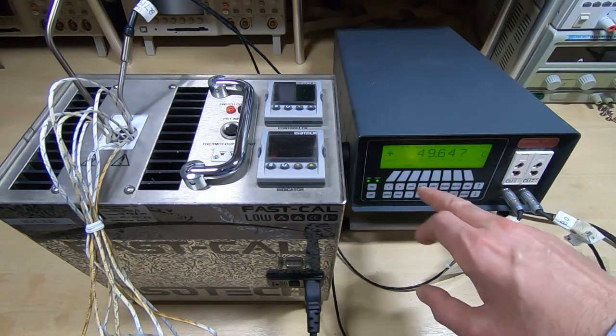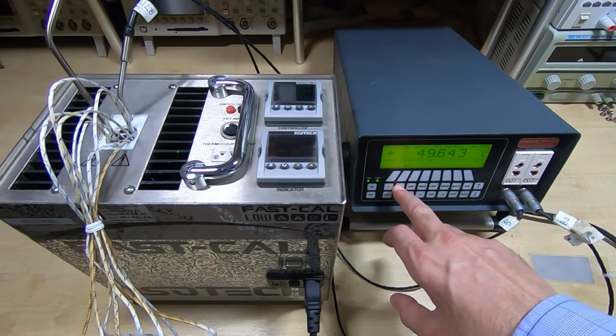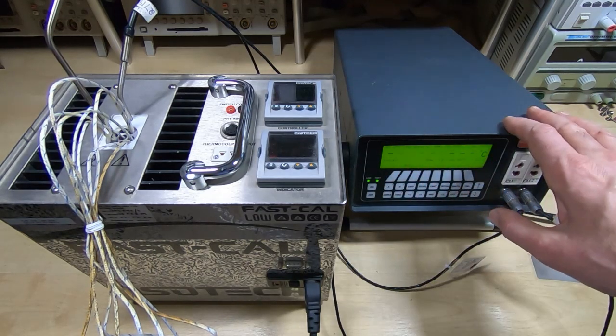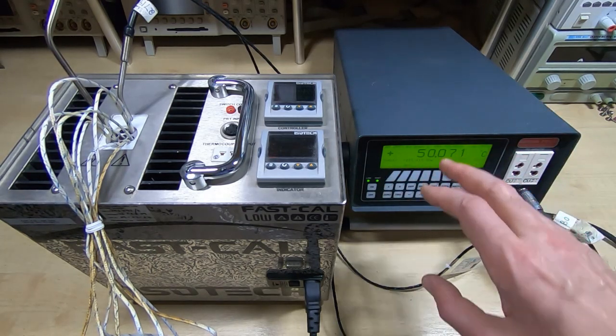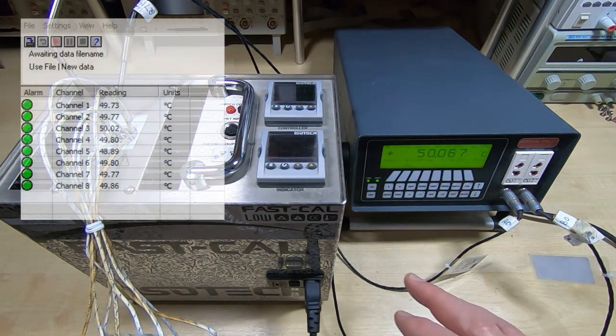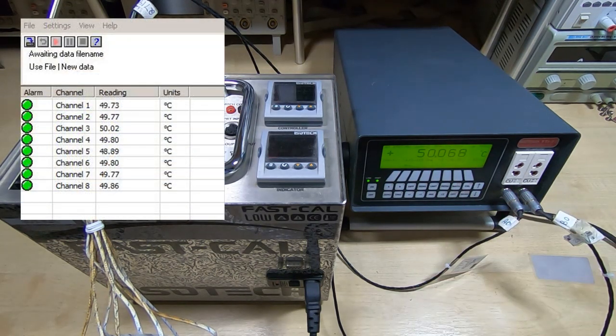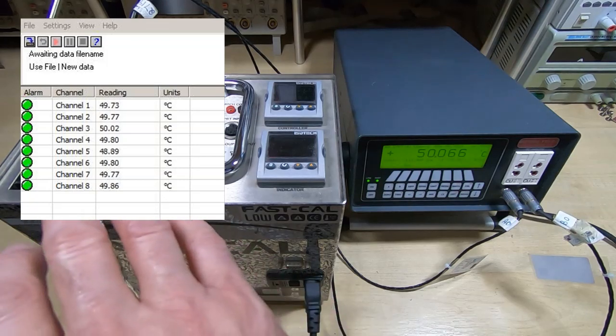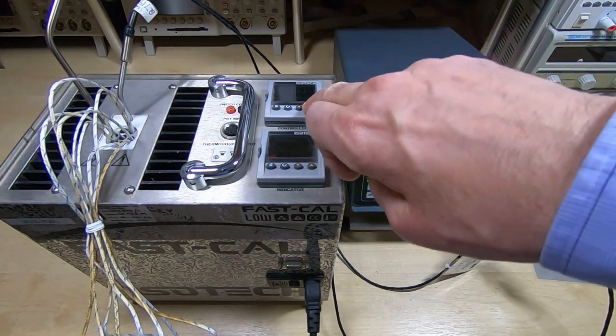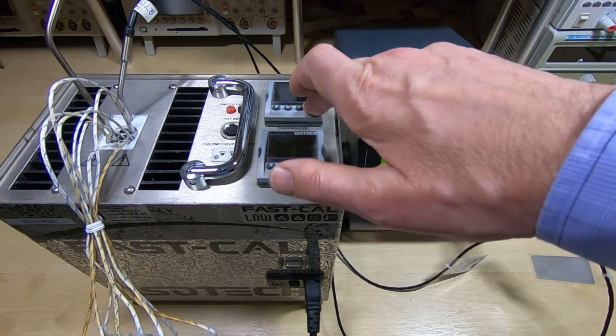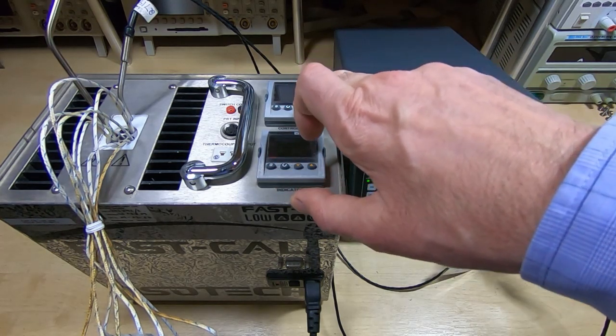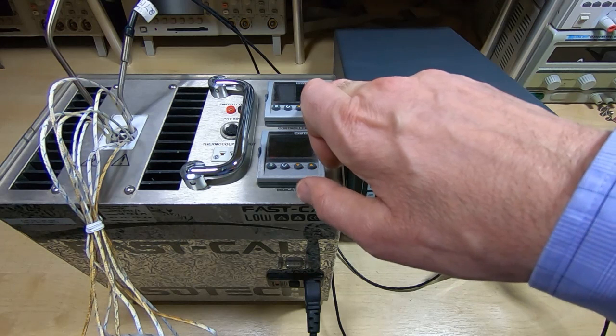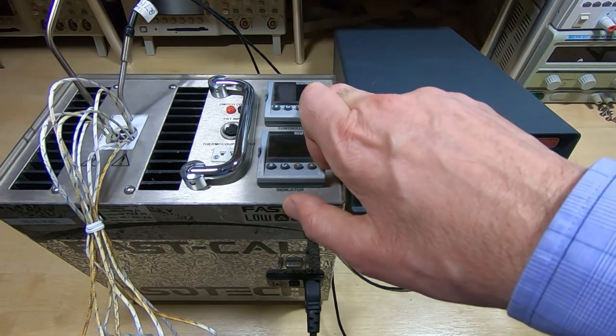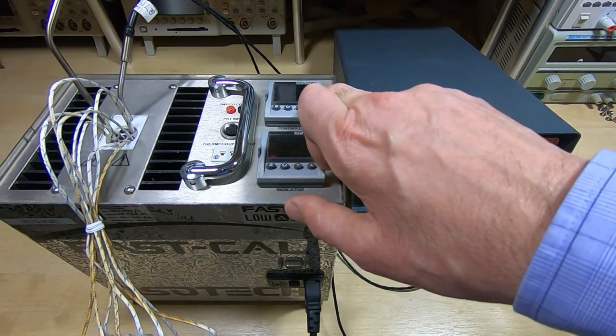So we'll take a snapshot at this reading. I am of course recording the 2 readings we're getting off the reference meter as well, so I can take the average of that, and then once I finish the entire run I can see what the overall error is for the probes that we're actually testing. So I'll now go up to 100 degrees. As I say, this won't go high enough for this particular application, so I'll make this the last one and then I'll transfer these into the actual high temperature dry well.